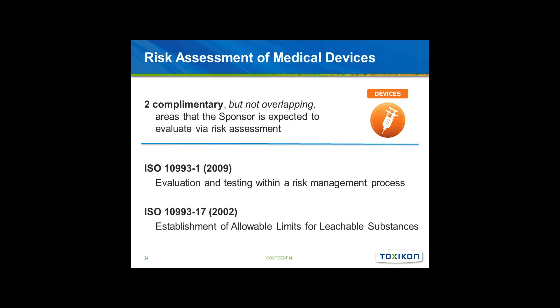The next piece is ISO 10993-17. Here we're establishing allowable limits for leachable substances. These leachable substances can be all sorts of different additives like we talked about, but more specifically for this presentation, it could be our colorants. So Part 1, as I mentioned, is where you evaluate the device materials, perhaps a component breakdown, consider history of clinical use, and identify the data gaps.